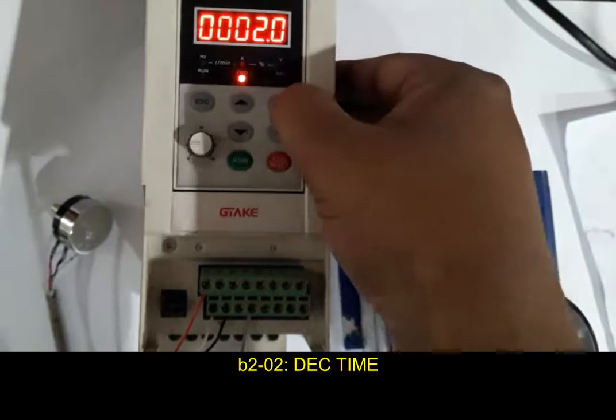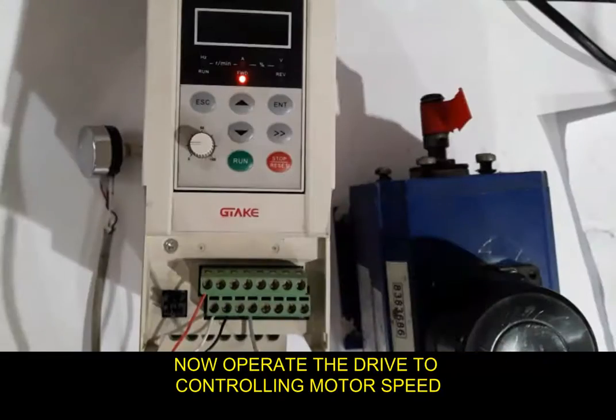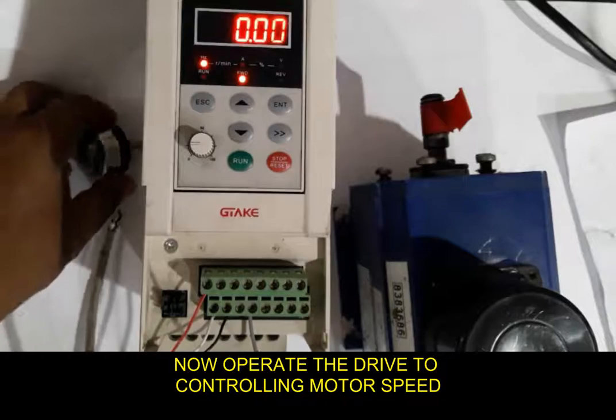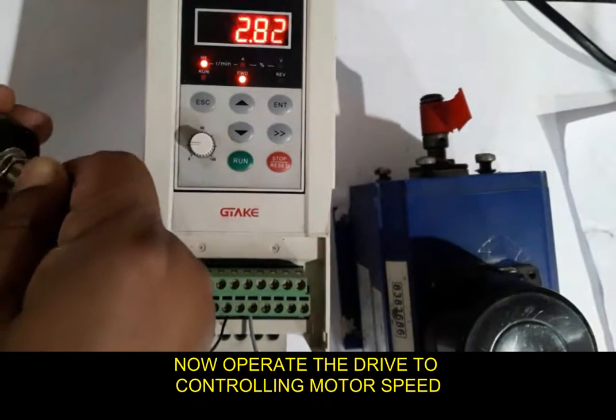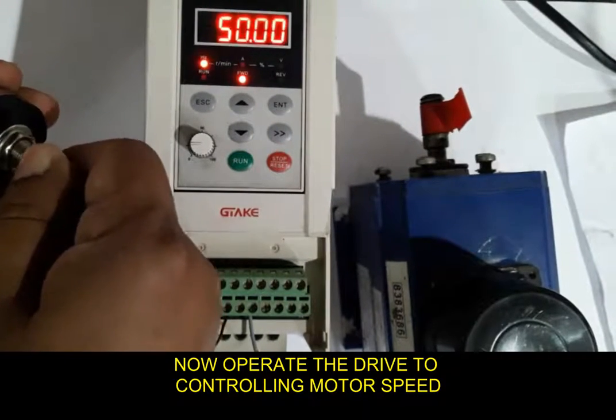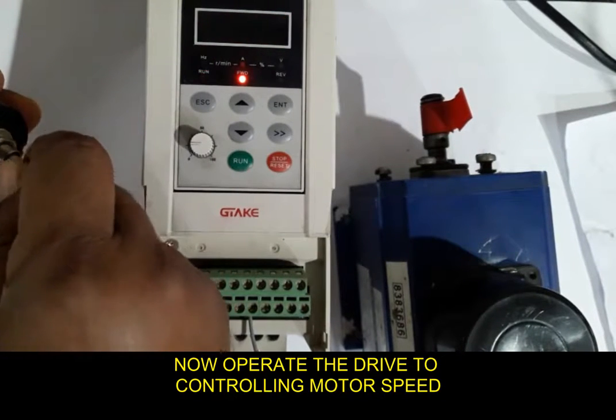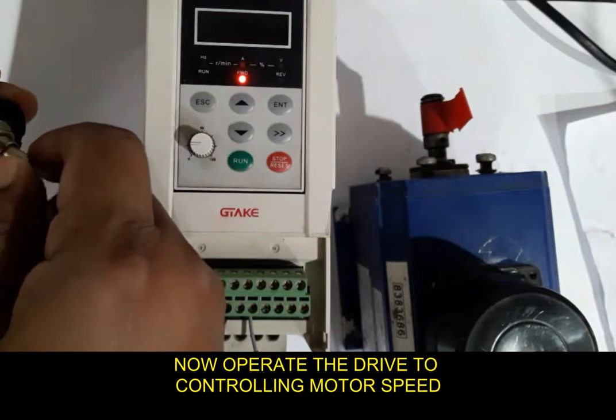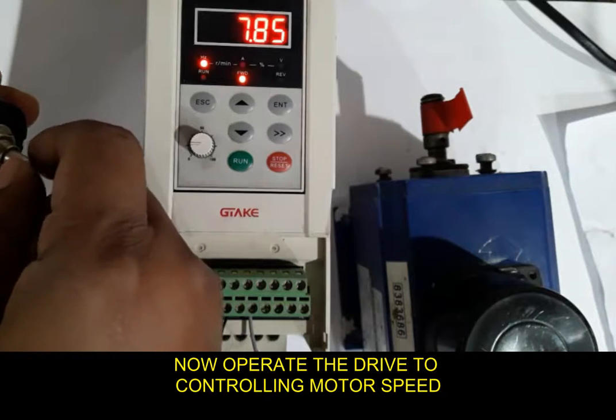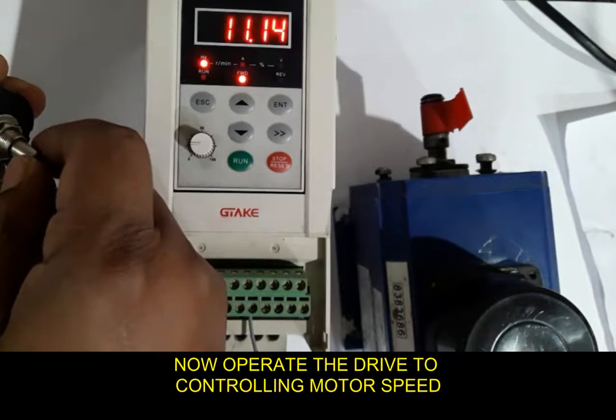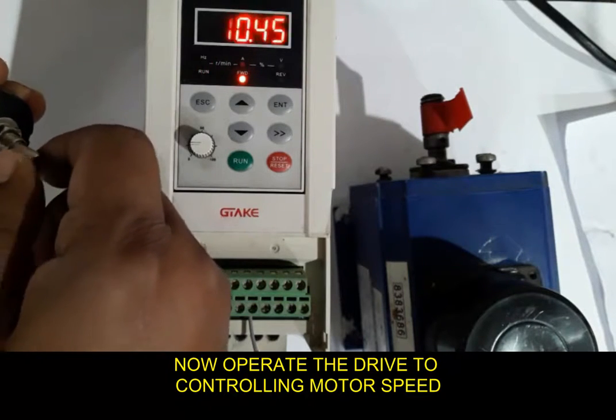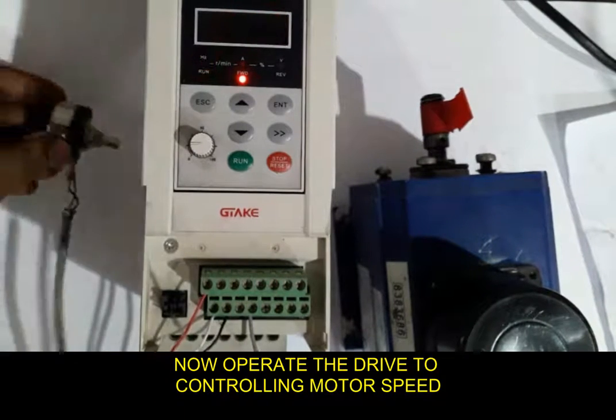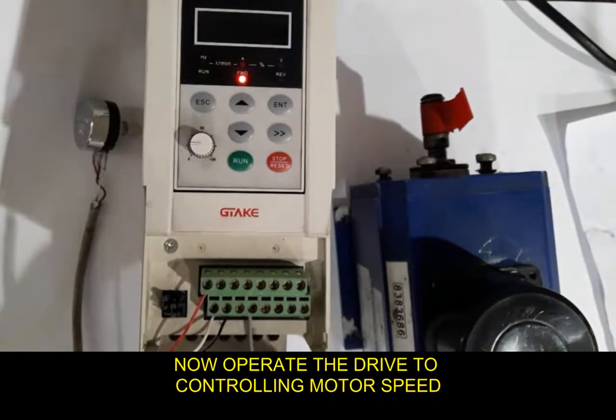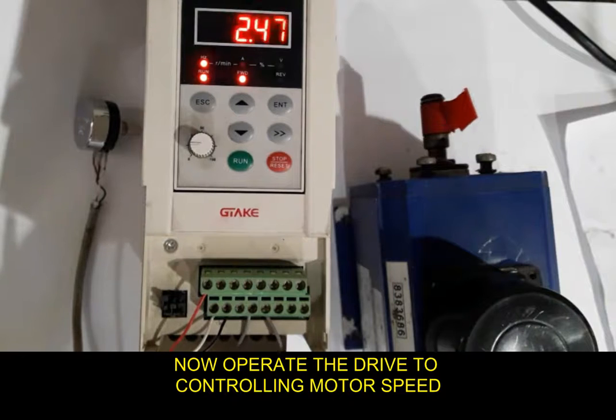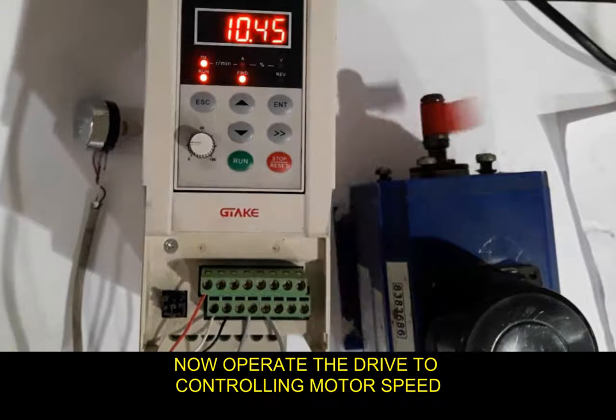This parameter we are setting for external operation in a machine. We are using a potentiometer for increasing or decreasing the speed variation, and common to X1 for run command. So here we are using an induction motor for checking whether the drive is okay or not. From common to X1, the motor is driven at 10 Hz frequency.